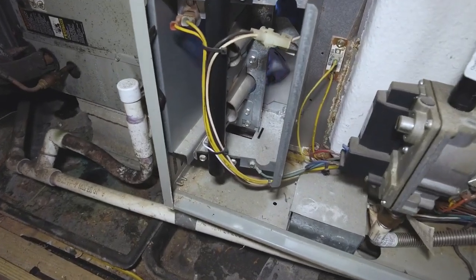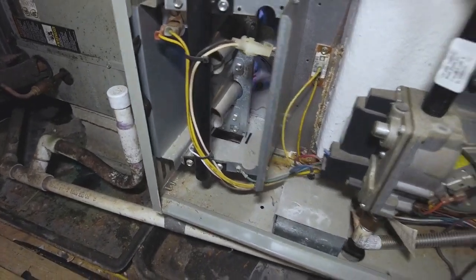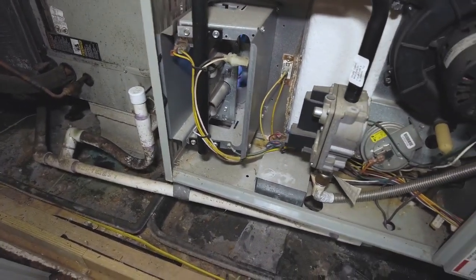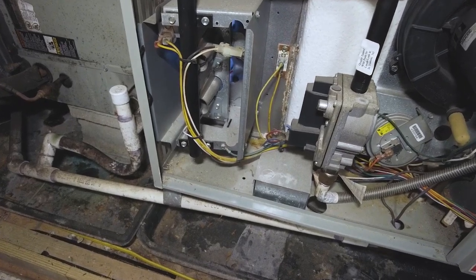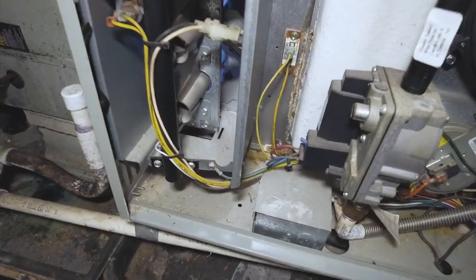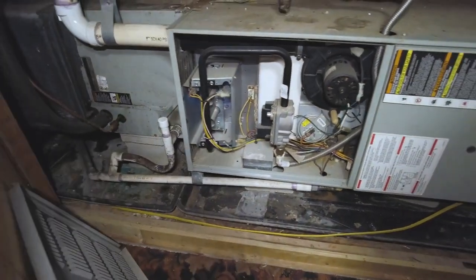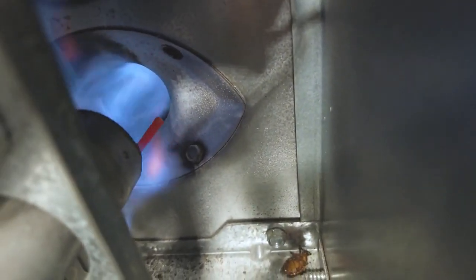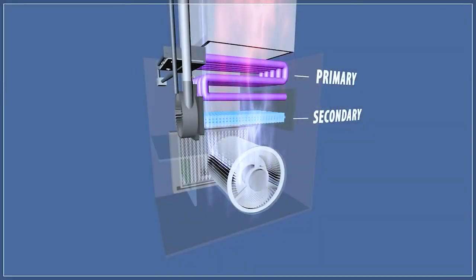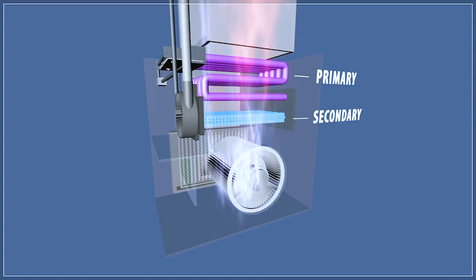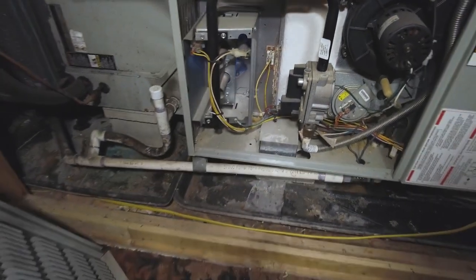Hey, welcome back. So in this video, I'm just covering a job I was at earlier this week. I found a crack in the heat exchanger. It's just a quick demonstration of how the flame looks whenever there's a crack in the heat exchanger and the blower fan comes on. It causes the flame to become more turbulent and distorted, just based off of the air actually infiltrating the internal portion of the heat exchanger.